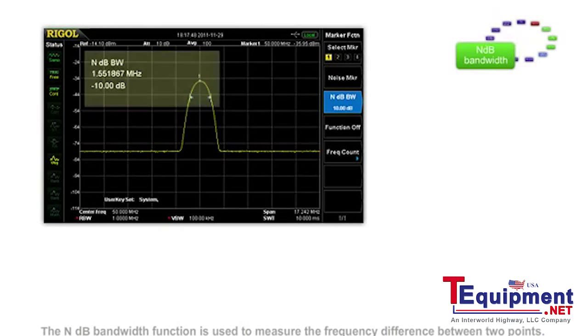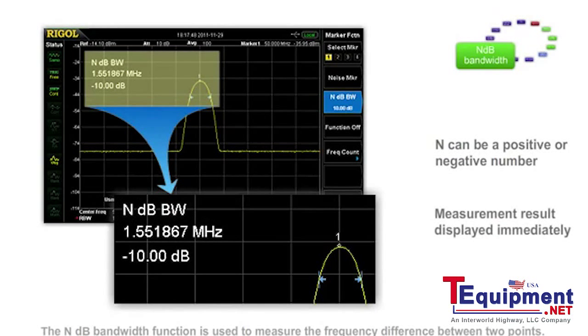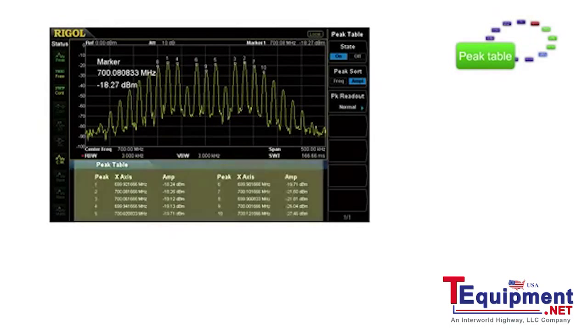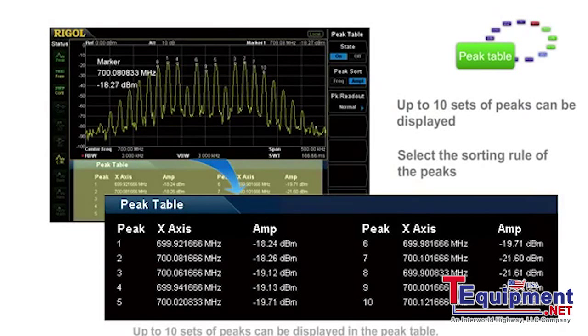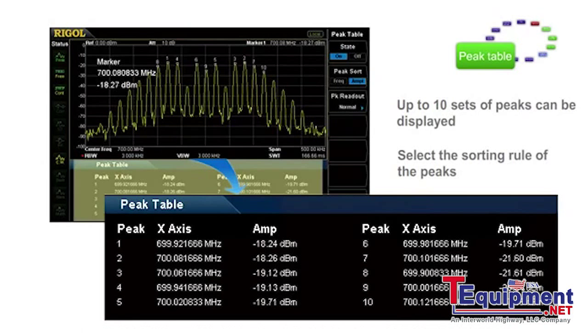The N dB bandwidth function is used to measure the frequency difference between two points. This can be shown using the convenient marker function of the instrument. Up to 10 sets of peaks can be displayed in the peak table. Users can select the sorting rule of the peaks and save the measurement results.